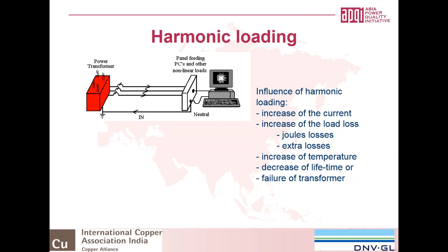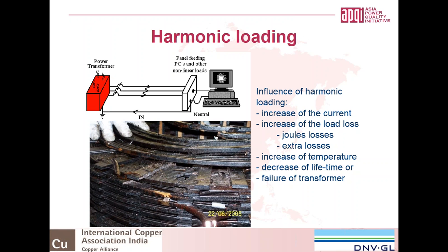If your losses are higher, then you will also see that your temperature will be higher. You will have an increase of your temperature. And an increase of your temperature means a decrease of the lifetime of the transformer, or probably a failure of the transformer. And this is a picture from more than 10 years ago. It was a transformer within the industry. You can see those are the windings which you have for several transformers, and there you will see some cooling channels, and you will immediately notice here that there was a flashover, right in the middle over there, and also where this board was normally placed.